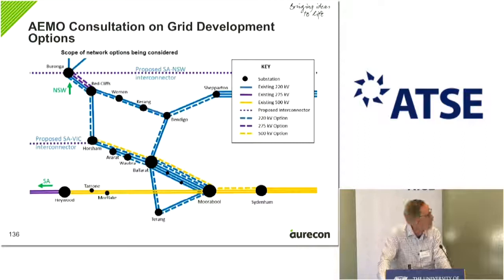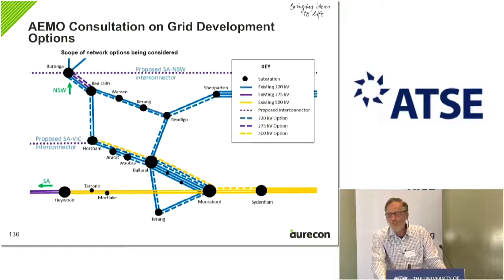The Heywood connection was uprated to handle 650 megawatts, but that's been downrated now because of what happened in the South Australian system black, where the rate of change of frequency when that line tripped was too great for the power system to handle.